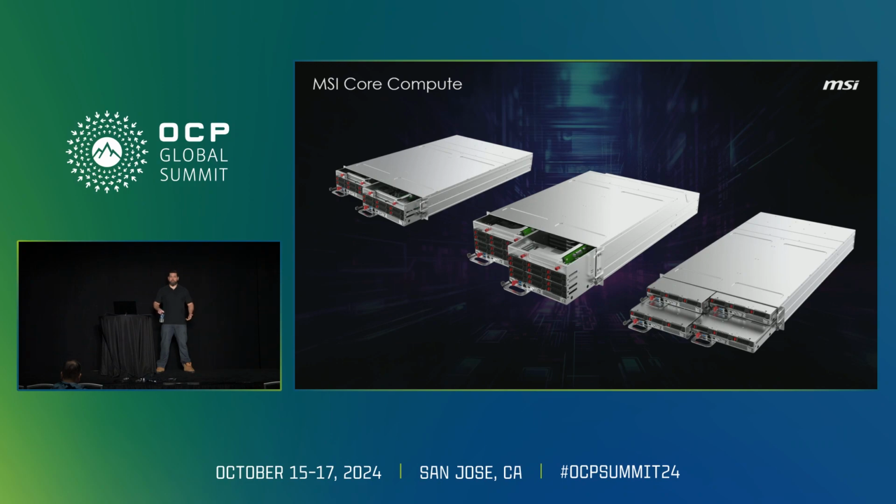Say you've got something more reasonable. You've got like a 12 kilowatt, 17 kilowatt, 8 kilowatt rack power budget. That's when you end up running out of power way before you run out of space. And I see a lot of racks that ship with just mostly blanking plates.